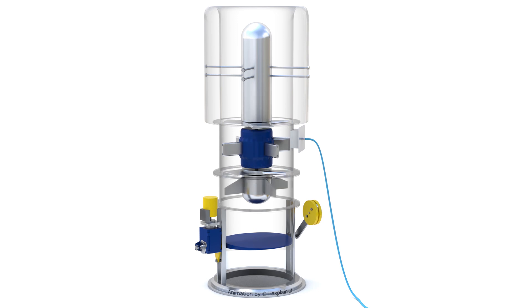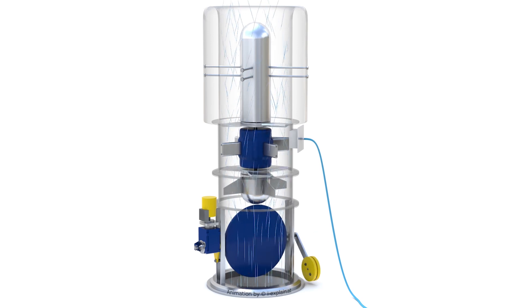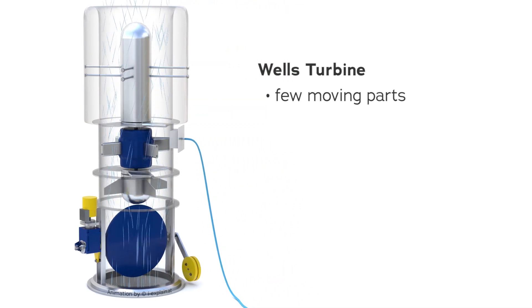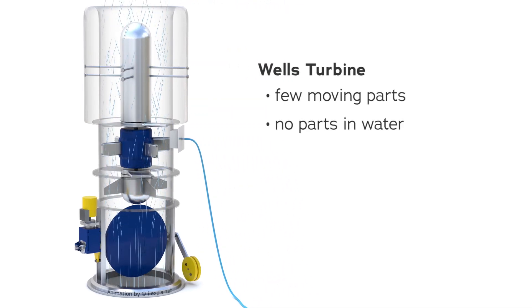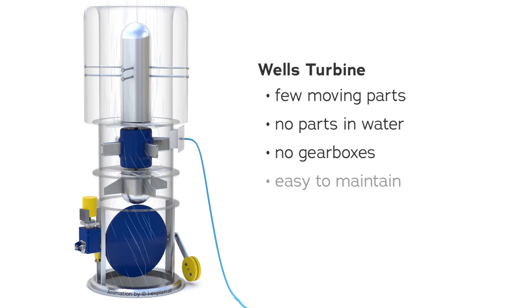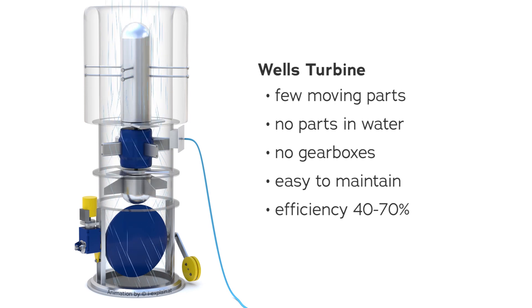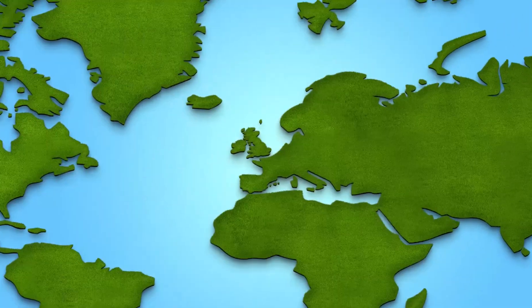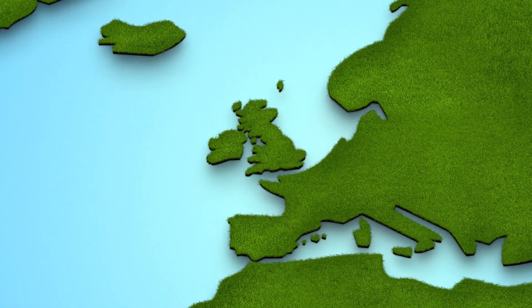This turbine is one of the simplest turbines for wave energy conversion. It has very few moving parts, none of them are in the water, it needs no gearboxes, is easy to maintain, and achieves an efficiency between 40 and 70%. This turbine has been tested in several research plants under real conditions.